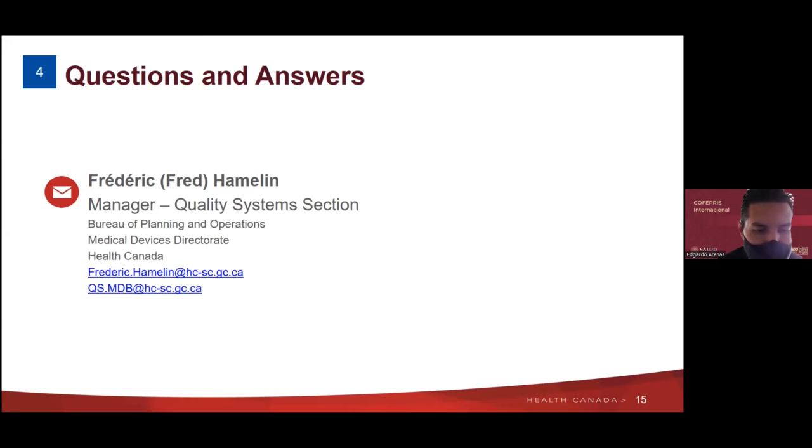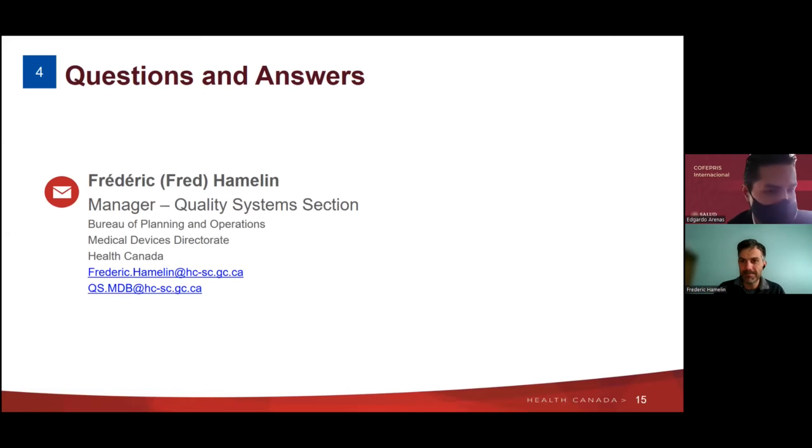Well, actually, I might be able to answer that. So for the first question, are registrars in Canada the equivalent to notified bodies in EU? This is something we've talked about for 20 years. The answer is both yes and no. In some cases, they are the same bodies. We recognize auditing organizations or registrars that are in fact notified bodies. For instance, DQS Med in Germany is recognized by us, but is also an EU notified body.